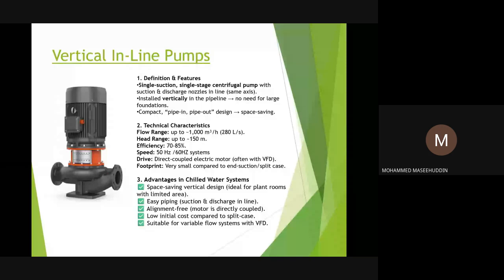So with these kinds of pumps, this is one of the biggest advantages today when it comes to optimization of the pump itself. Even in chilled water pumps, these things were not available. When we started using those pumps, we were using them only on the manual side. They were not even used with VFDs. So luckily, now we have a lot of development in technology, and a lot of IoT enabled things, which give us a clear indication, save a lot of time and energy, and are more economical in the long run.